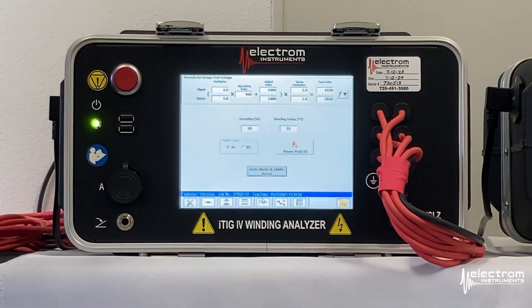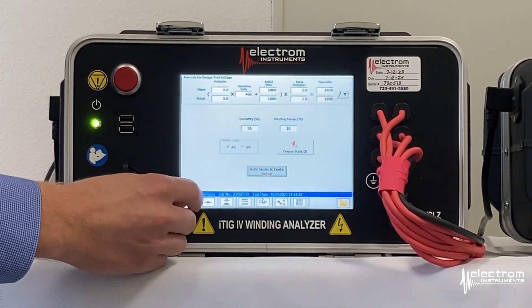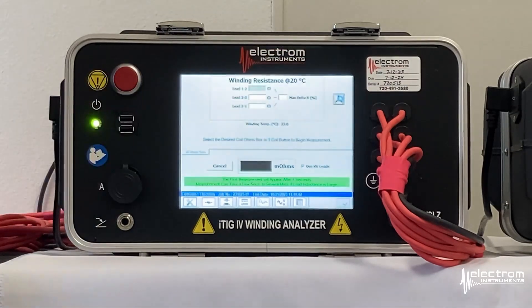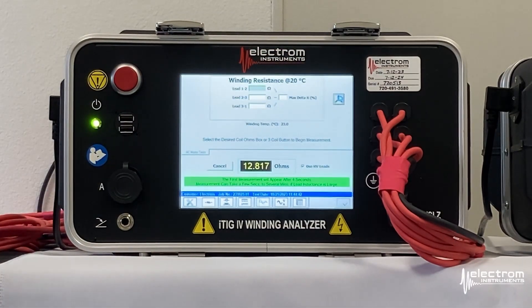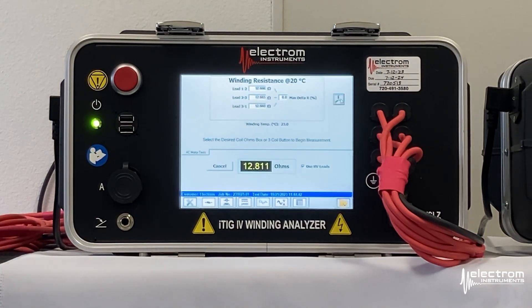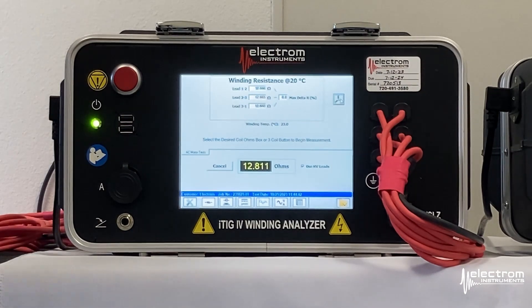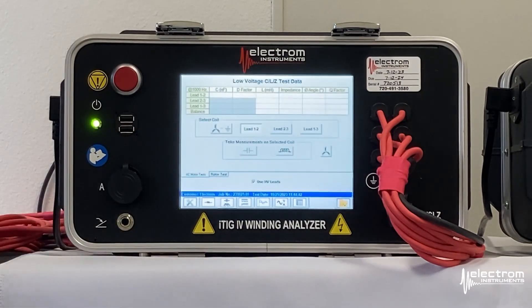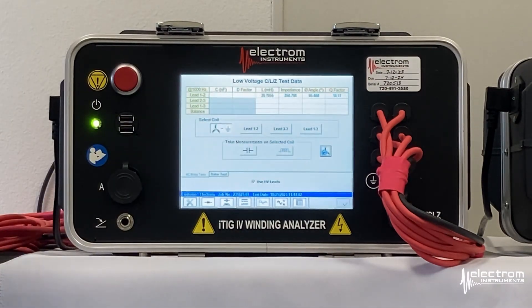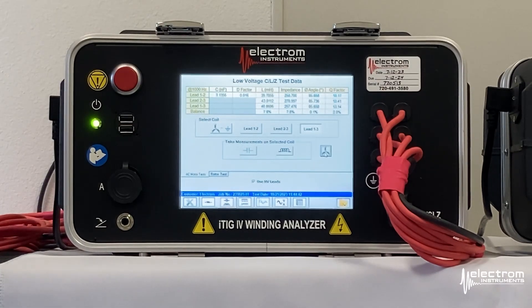Now we have our leads connected to the motor and we're ready to start our test set, working from left to right on the tabs along the bottom row. First up is our winding resistance measurement. Click the star coil symbol and the instrument will go through and measure winding resistance in all three phases and then calculate the max delta. Next up is the optional capacitance, inductance, and impedance measurement — the instrument measures these in all three phases and gives you the balance of each measurement.